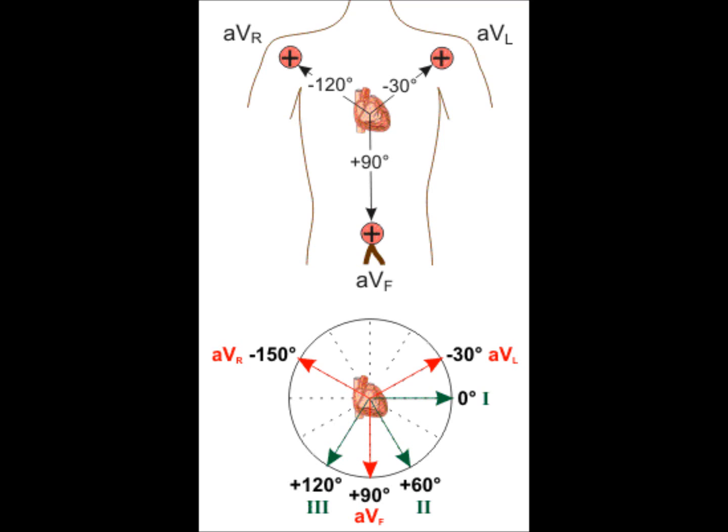Electrical potential produced is very small in the augmented limb leads. As a result, the ECG machine augments the amplitude of the electrical potentials detected at each extremity by about 50%. A stands for augmented. In cases where we have AVR, AVL, AVF, it refers to augmented voltage and then location. AVR is augmented voltage right arm, AVL is augmented voltage left arm, and AVF refers to augmented voltage left foot.